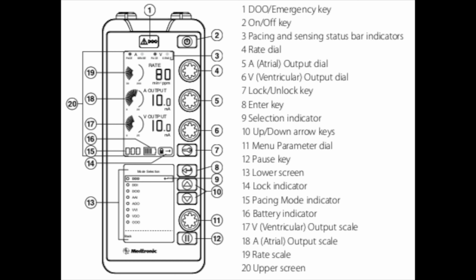To turn off the temporary pacemaker, do the following. 1. Unlock the temporary pacemaker if it is locked. 2. Press the on-off key once. A message is displayed in the lower screen to confirm temporary pacemaker shutdown. 3. Press the enter key once within 30 seconds to confirm temporary pacemaker shutdown. Note: if the enter key is not pressed, the temporary pacemaker remains on and continues to pace at the currently selected values.